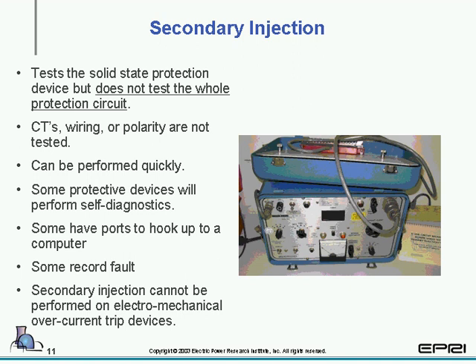Secondary injection. In between electromechanical and the self-diagnostics, we had the solid state design. When this design came out, they came out with units that would simulate a fault into the protective device. The only challenge with these designs is that they do not check the CT, the wiring, or the polarity of the inputs to the protective solid-state device.